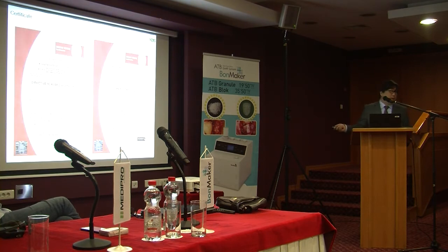This is a medical device in Europe. And only we acquired this BonMaker as a medical device. It is the same class and the same grade as a dental implant. This is a class 2B product.